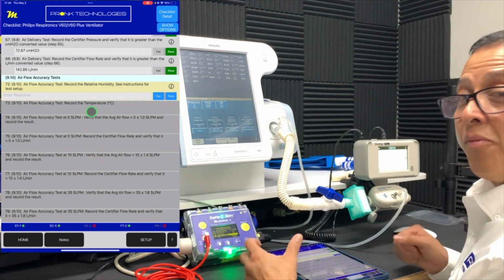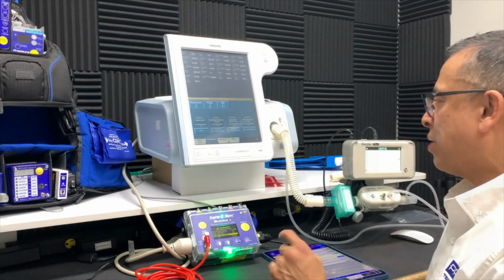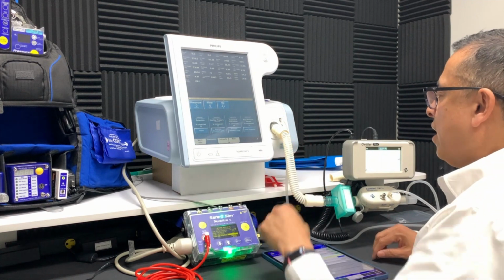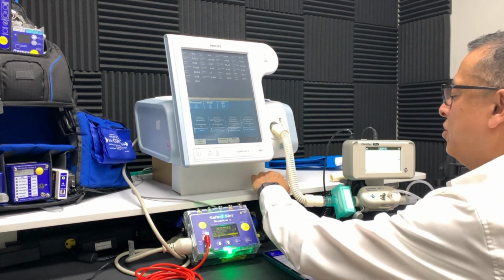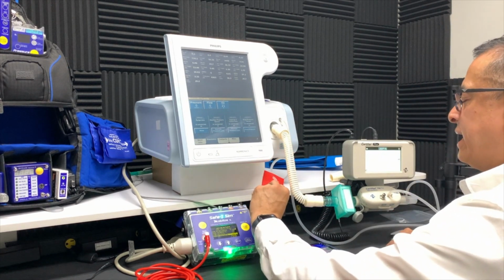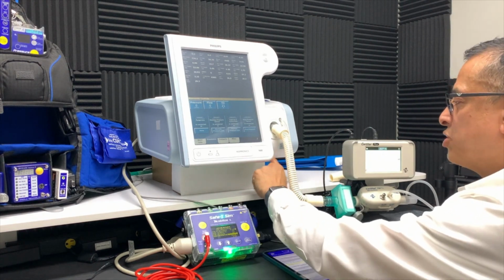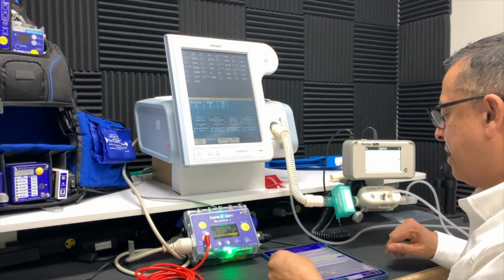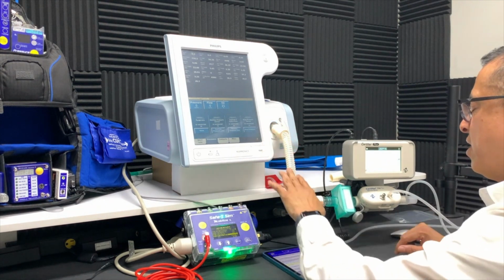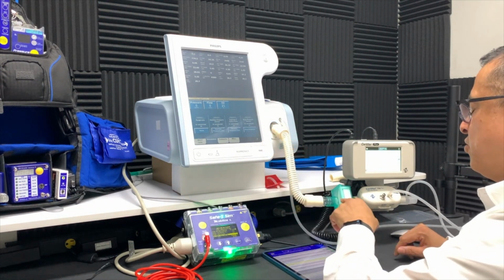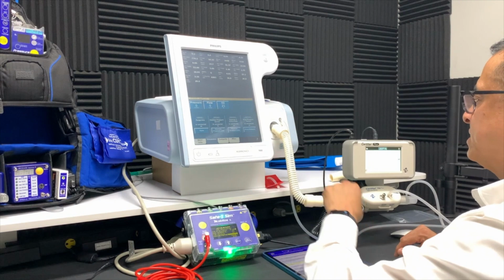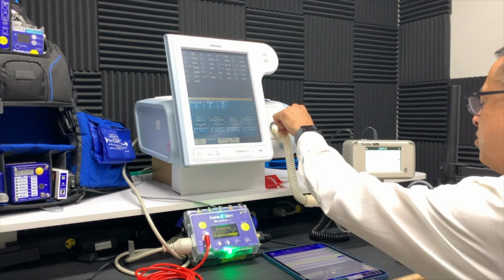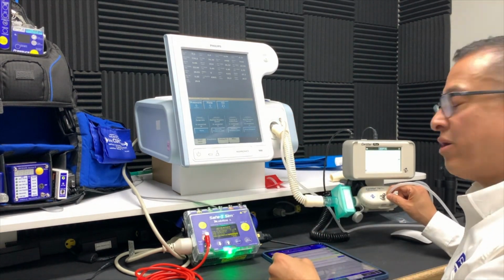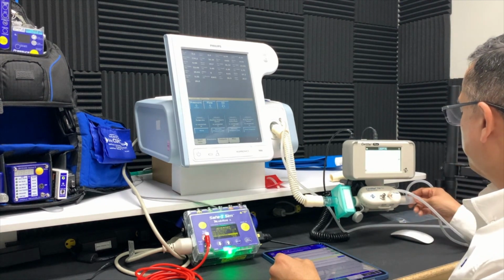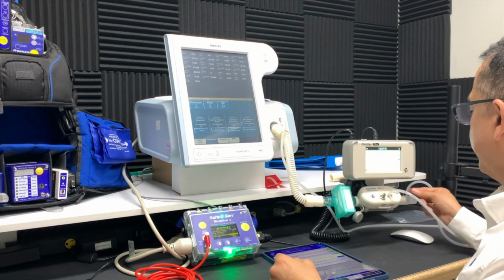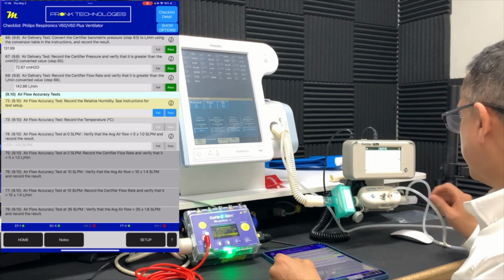Now we can go ahead and perform the airflow accuracy. In order to do these properly, we want to make sure we've configured our ventilator properly by utilizing the plug adapter here to the bottom of the ventilator to make sure we seal that off. So that's the requirement from the manufacturer. We also want to configure the tubing into our analyzer via the filter like we have in the past. We're going to monitor pressure from the proximal port over to the flow meter, the pressure port, as well as the pick-off pressure is going to be monitored from the output here by connecting these three things together.